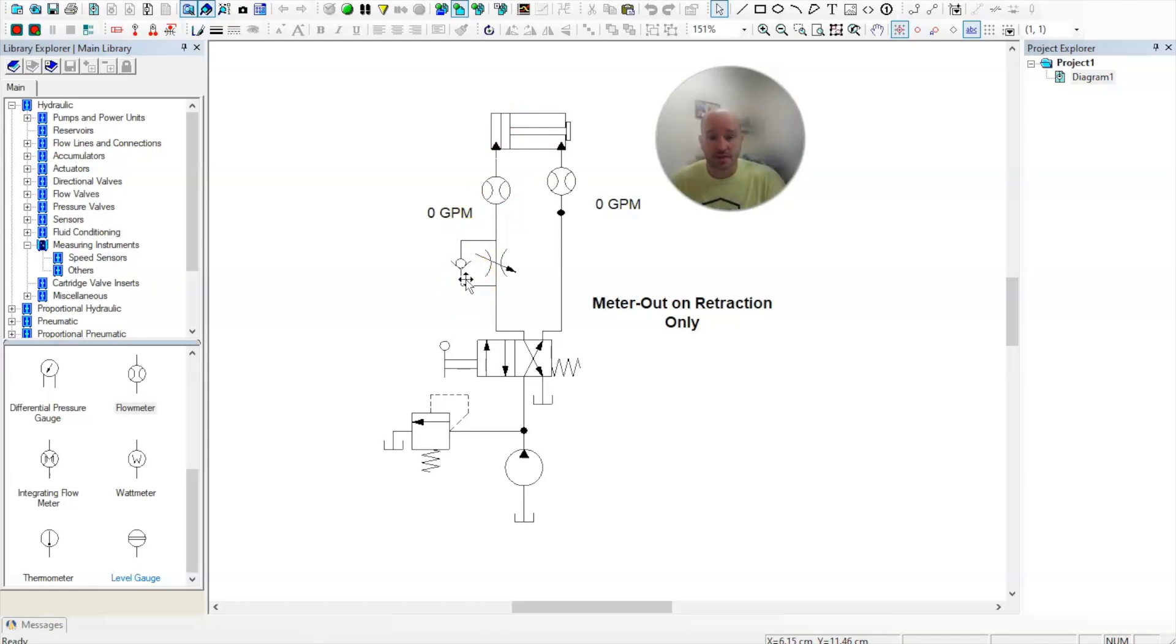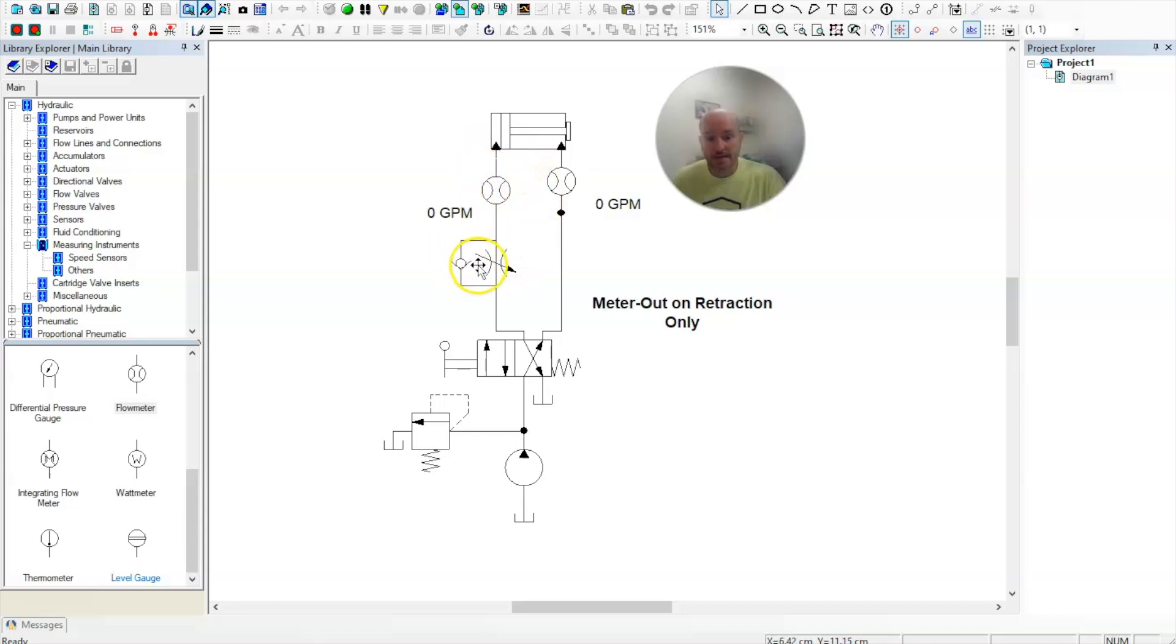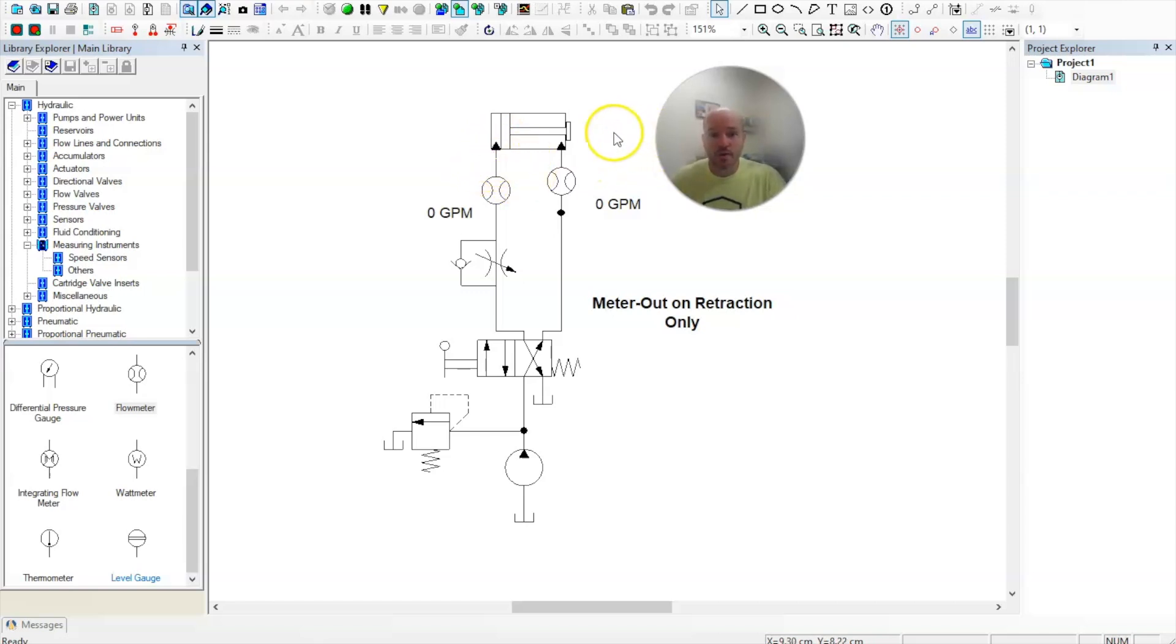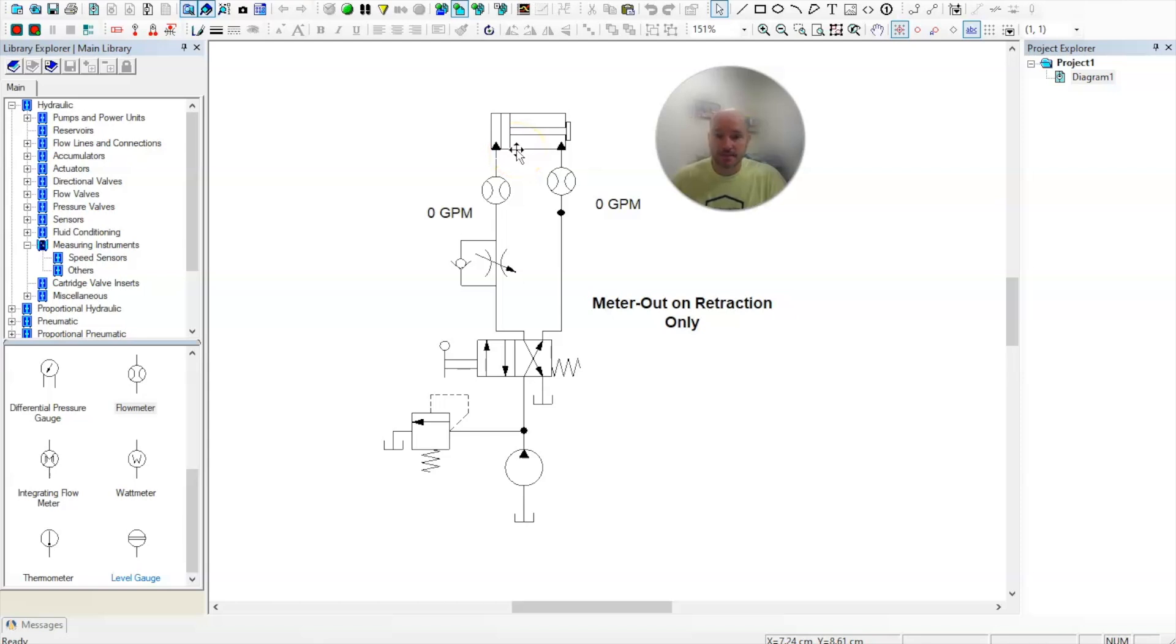Then the next question is, is it going to meter the cylinder as it's extending or it's retracting? Well, this output that it is tied to is an output when it's retracting. When it's extending, this port A here is an input, not an output. So that's how you have to establish this. Here's your output. When this goes to retract, all the oil comes out of here. This port is an output. So that's why it's metered out on retraction only.